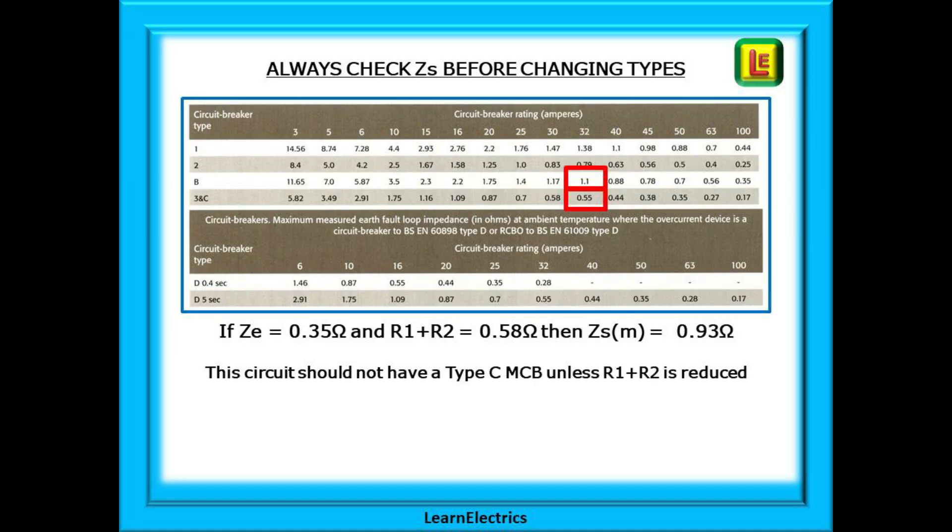Look at this example where we have a 32 amp MCB type B installed. In this circuit ZE is 0.35 ohms and the internal R1 plus R2 is 0.58 ohms. Add the two together and our ZS M is 0.93 ohms and this is fine for a B type. If we wanted to change to a C type then the maximum ZS would be 0.55 ohms for that circuit. We cannot install a 32 amp type C MCB without first reducing the ZS to 0.55 ohms or less.